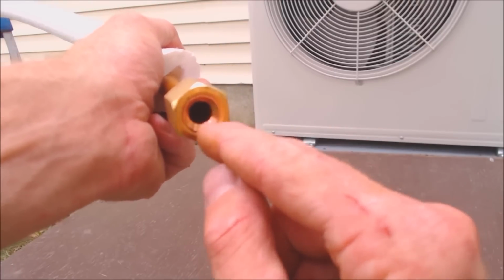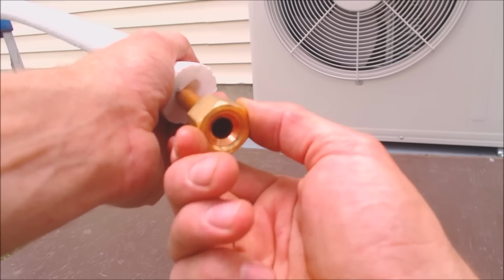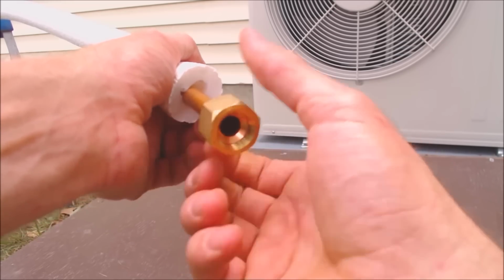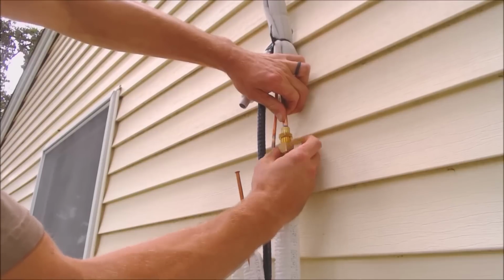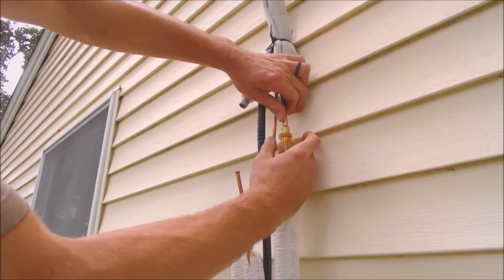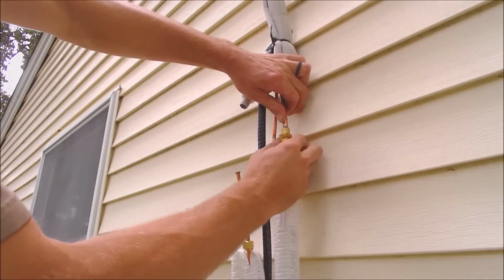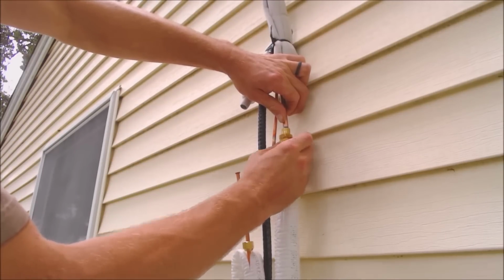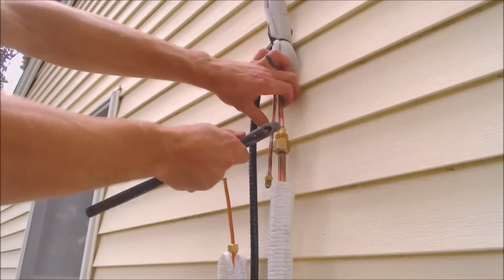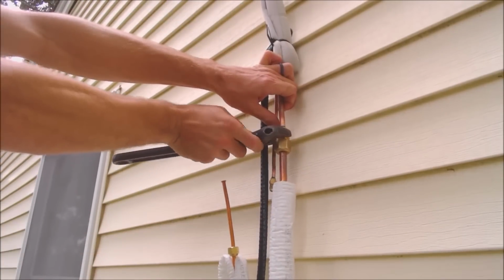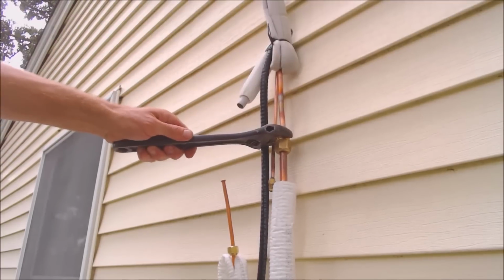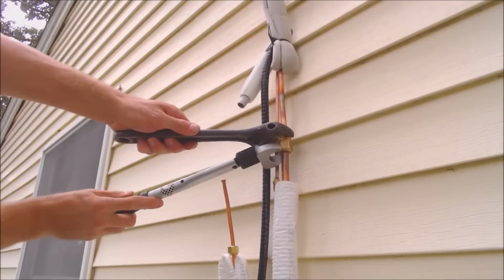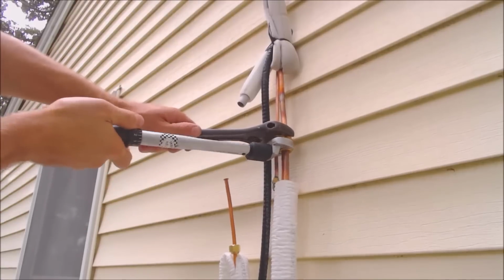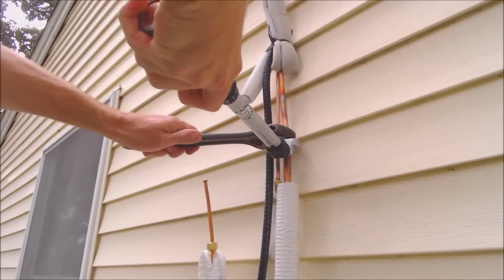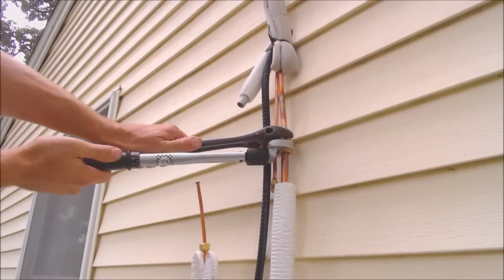Make sure it's a 45-degree flare. You fit it to the flare face. Everything looks good. You then hand tighten your flare nut onto the flare face. It's usually on a two-way or three-way service valve. You're tightening it down, and you're going to hold your service valve with a wrench, a backup wrench, maybe an adjustable wrench, but you just want to make sure you're holding that. And you're going to use a torque wrench to tighten the flare nut down to the specified torque value for the copper tube diameter size.